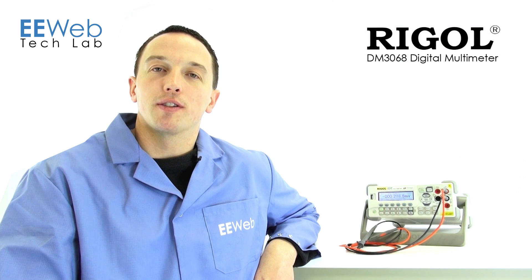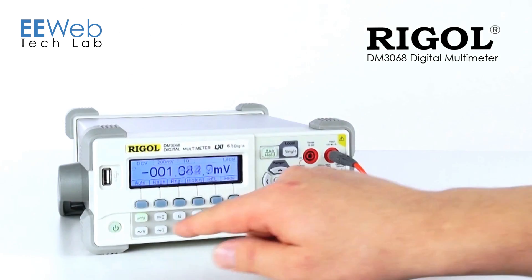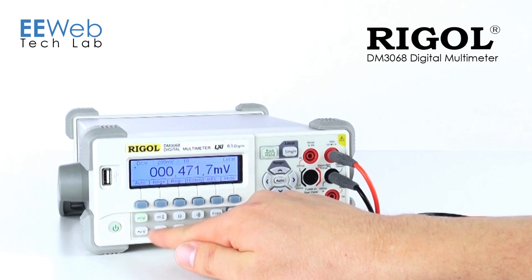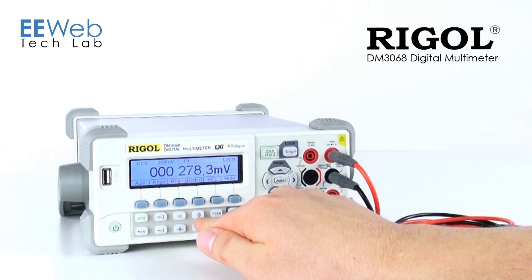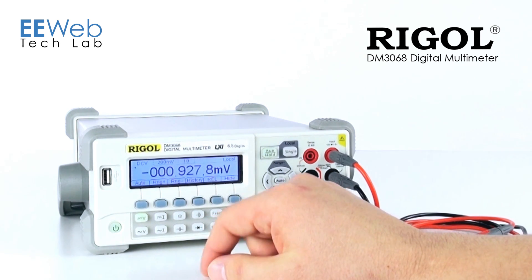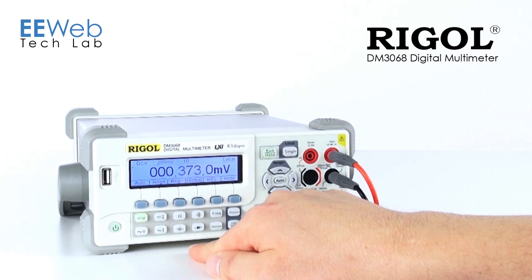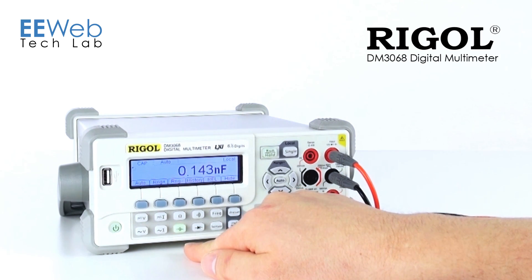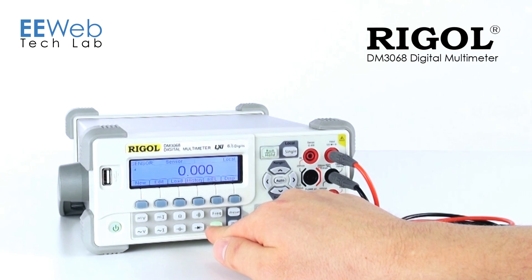Let's take a look at the measurement functions. You have all of your standard measurement functions: DC voltage, DC current, resistance, AC voltage, AC current, continuity, and frequency. But Rigol includes a couple that you don't typically see on a low-cost DMM, and that is a capacitance meter as well as some thermocouple functions.